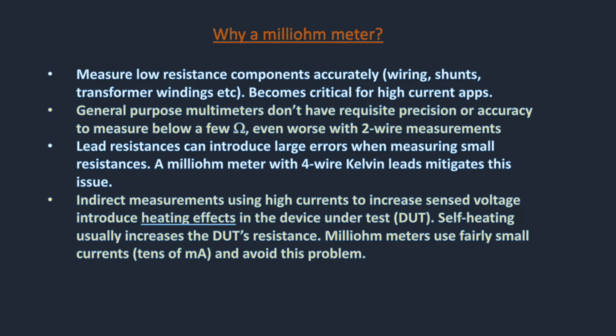So let's look why we need a milliohm-meter. Anytime you want to measure low resistance components accurately, such as wiring, shunts, transformer windings, anything that carries high currents, for example, typically will have low resistance, so you want to measure those. General purpose multimeters don't have the requisite precision or accuracy to measure anything below a few ohms, even worse when you have a two-wire measurement. Lead resistances in the meter itself can introduce large errors when measuring small resistances.